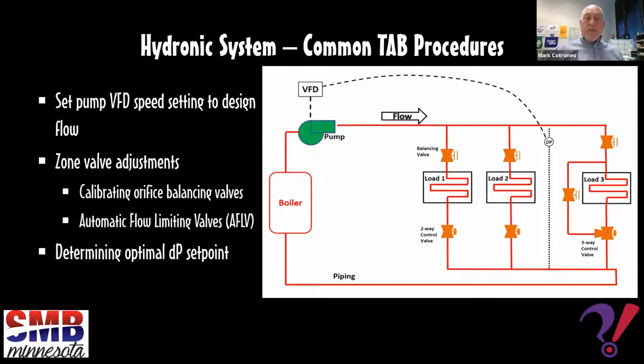For a variable volume secondary pump, we would start by indexing all the control valves in the system to fully open. Then go through the process of establishing the shutoff head and dynamic head by plotting on a curve. If the system employs calibrated balancing valves, each one is then systematically adjusted to provide the design water flow at each user. After all the valves are set, the dynamic pressure of the pump will need to be remeasured and plotted on the pump curve to read the pump flow. And the VFD is then adjusted to achieve total design flow.